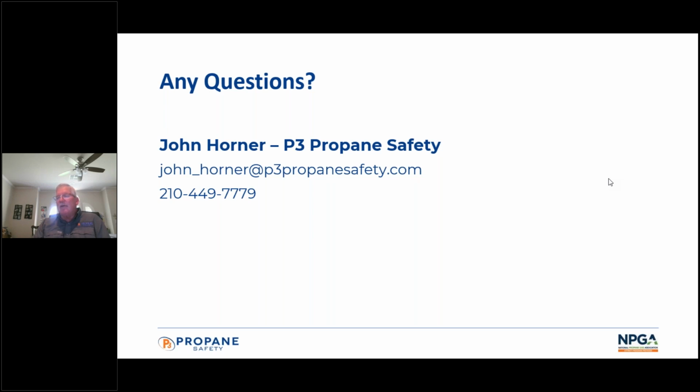been going on. We did have a customer who had a DOT inspection. They found out they were doing their monthly meter creep tests incorrectly. You could easily tell by the paperwork that it was being pencil whipped by everybody there. They had a total of 12 bobtails, and their fine ended up being just a little over $160,000 because they had pencil whipped them all. All the paperwork that they had given the inspector was easy to prove they were pencil whipped because they were all filled out and they all had the same mistake on them.